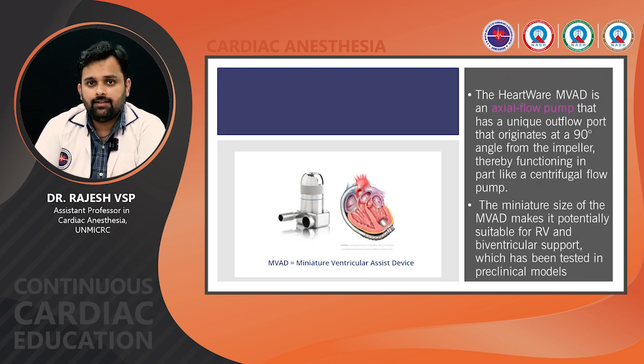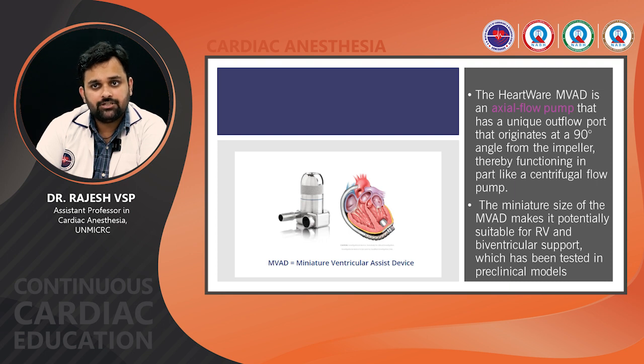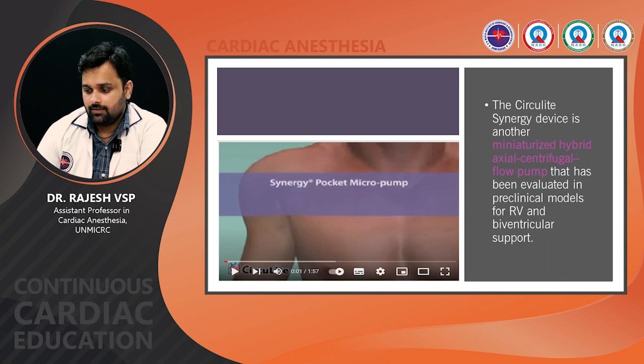Coming to the HeartWare MVAD, that is the miniature ventricular assist device, it has a unique outflow port that originates at a 90 degree angle from the impeller, thereby functioning in part like a centrifugal flow pump. The miniature size makes it potentially suitable for RV and biventricular support, which has been tested in preclinical models. This is not approved for clinical use in the United States. The other one is the Circulite Synergy device, which is also a miniaturized hybrid axial centrifugal flow pump that has been evaluated in preclinical models for RV and biventricular support. And this video is depicting the pump.